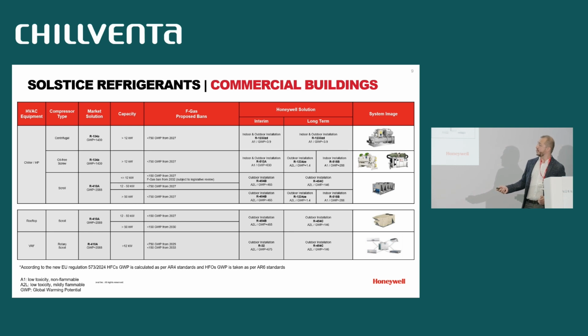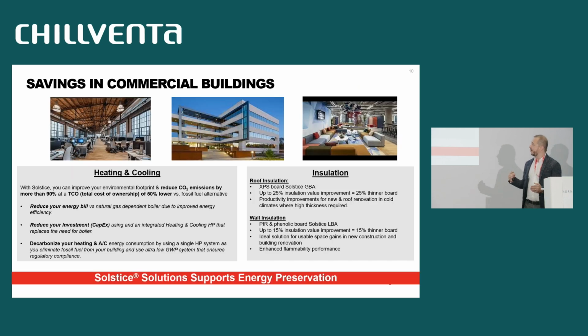For the high pressure equipment type, the rooftop and VRFs, we see more and more OEMs use 454B as well as R32 in VRF systems. And 454C, we believe, provides the right solution below 150 as a long-term solution that provides the right temperature levels, as well as the right GWP, which will provide compliance and the right temperature output for these product types. So overall, when it comes to heating and cooling demand, we see significant savings from the use of HFO systems and heat pumps, with more than 90% at total cost of ownership, and that will be 50% lower than fossil fuel alternatives. And I will touch on this in a couple of slides with real case scenarios.